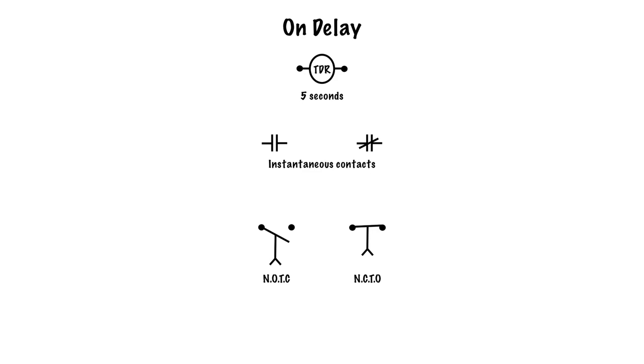Now an on-delay relay is like any other relay. It will have a coil and a set of contacts. The difference is, not only does it have a set of instantaneous contacts—a normally open set and a normally closed set—which close or open instantly when the coil energizes, but it also has a normally open time to close and a normally closed time to open contact.